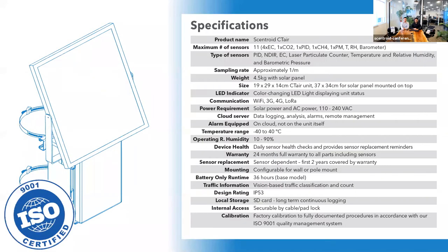Let's briefly go over all the specifications. The unit samples air from the top of the unit, pulled through the sensors and exhausted at the bottom. The maximum number of sensors is 11: four electrochemical sensors (chosen from our sensor list), one CO2 sensor, a PID sensor, a methane sensor, a particulate sensor, as well as temperature, humidity, and atmospheric pressure sensors.